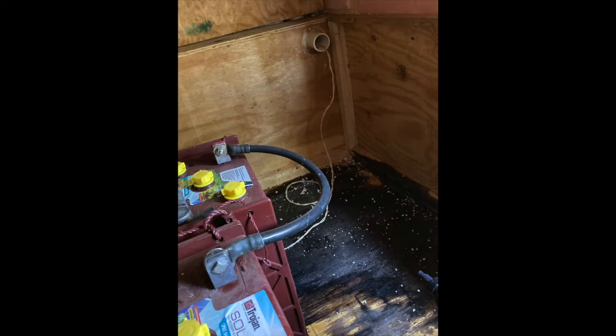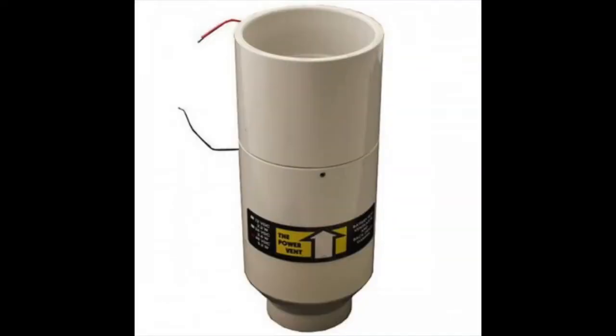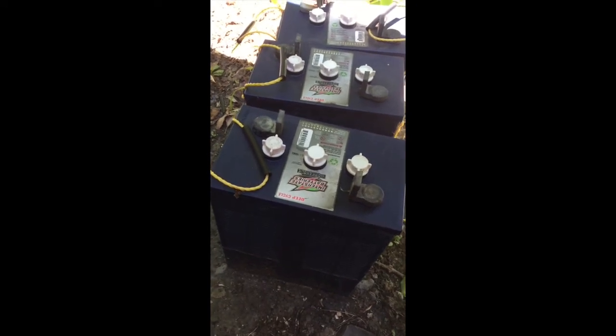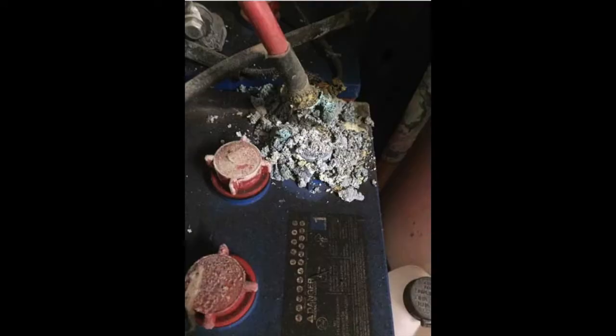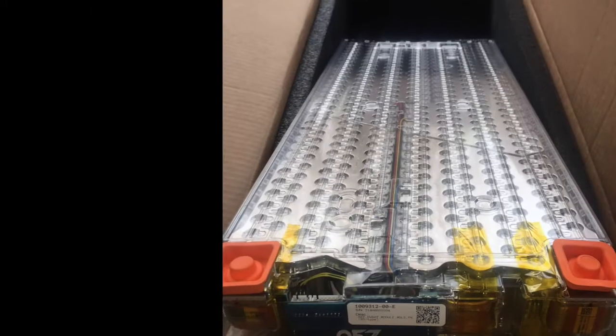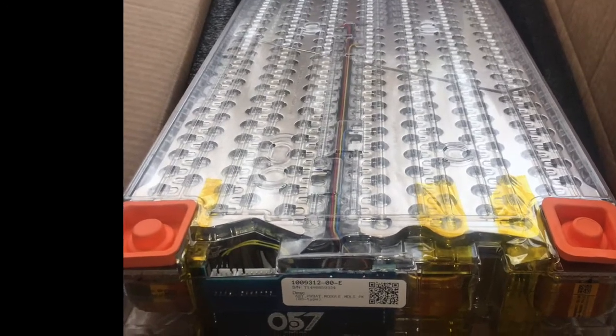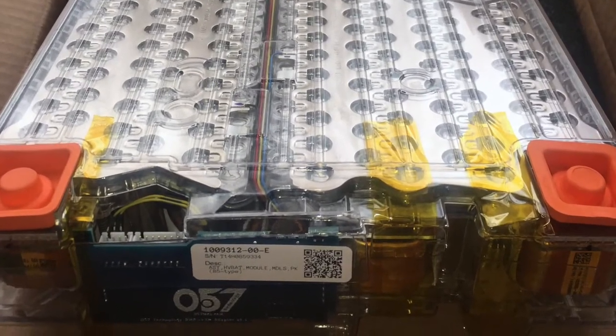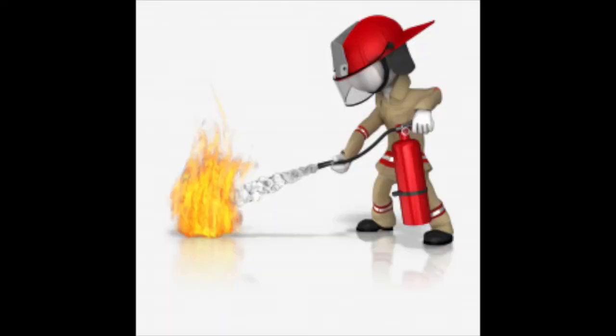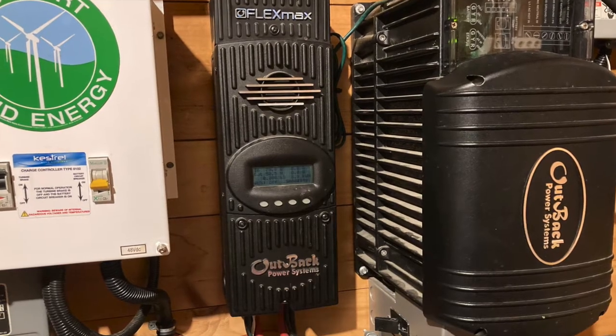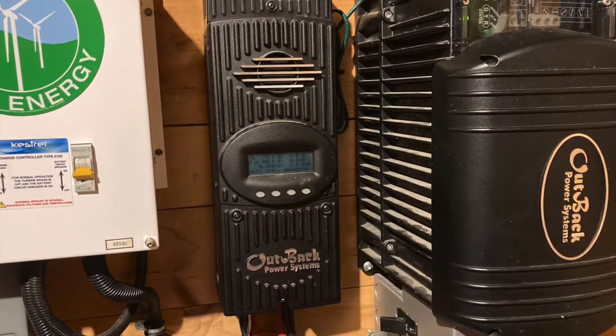And of course, the gases produced by lead acid need to be removed from indoors and vented outside. Plus, they don't last as long as lithium, and they require frequent maintenance like watering and making sure that the cables and connections remain corrosion-free. Lithium batteries have none of those problems, but they do have drawbacks. Two of the most important considerations are cost and safety. Lithium costs far more than lead, and they behave quite differently, meaning that the equipment that you have may not be compatible with the different voltages and charge profile that lithium requires.